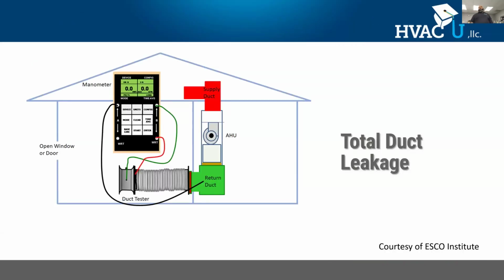All right, so here's a picture of the total leakage test. Again, with the total leakage, I'm just looking at the ducts. How bad are they leaking? One of my reference points is going to be what percentage of total CFM air handler flow I am leaking. Some energy codes actually look at the duct leakage in CFM per square foot, and you'll find that in some energy code requirements. The moral of the story for total duct leakage: how much leakage do I have?